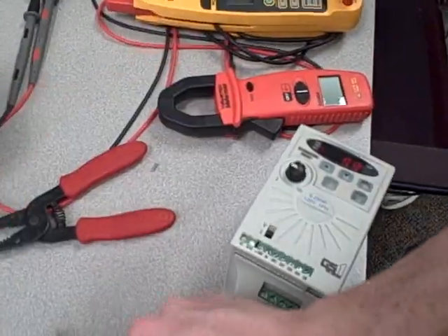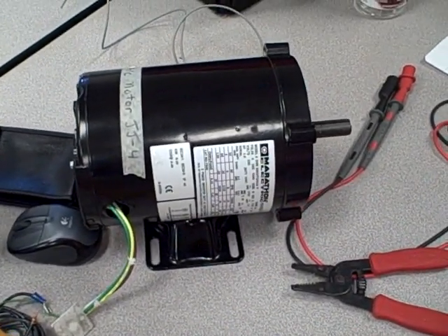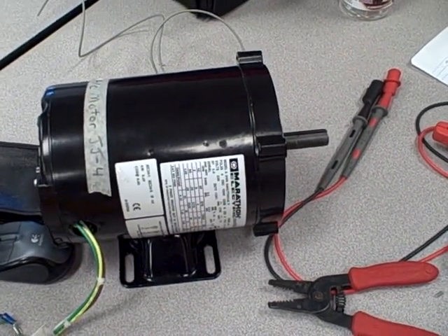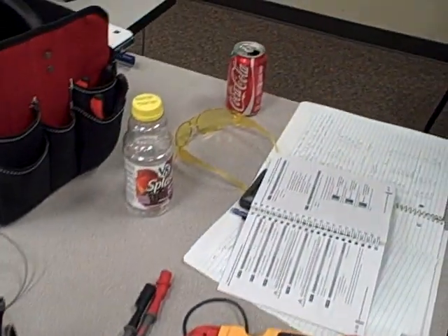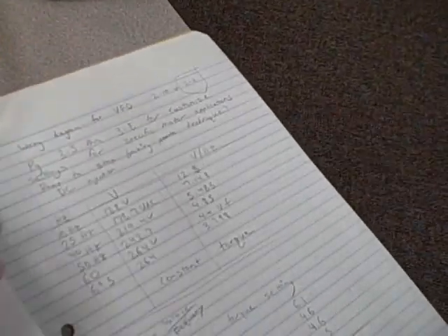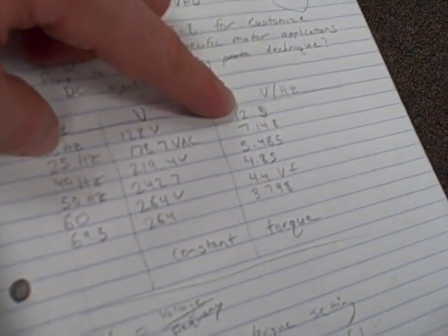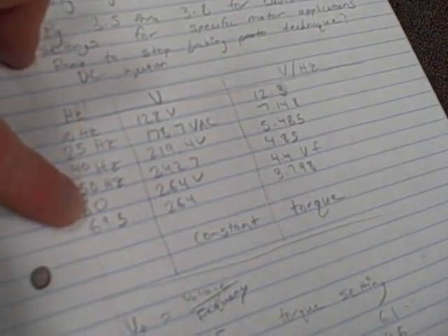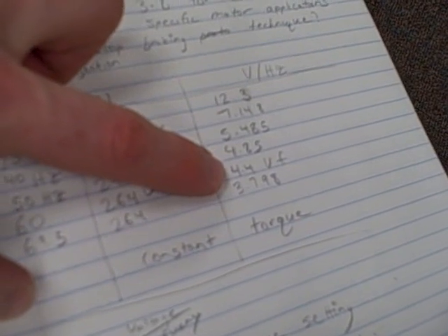Now, we can also configure different profiles for the volts to hertz ratio in the drive. What we're looking at here is just one of the available profiles. You could set this up, for example, for a high starting torque application, in which case it's going to give a greater volts per hertz at the lower end than at the high end. So right here, these are the numbers we got for our high starting torque. We got a 12.3 volts to hertz ratio at 10 hertz, and then as we sped the thing up and finally got up to 60 hertz, it dropped back down to the normal 4.4 volts per hertz ratio.